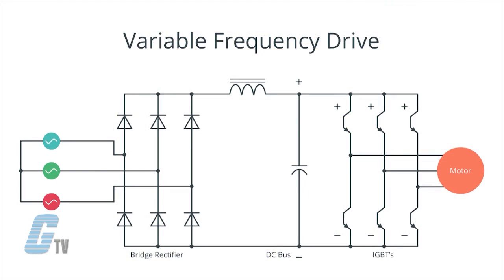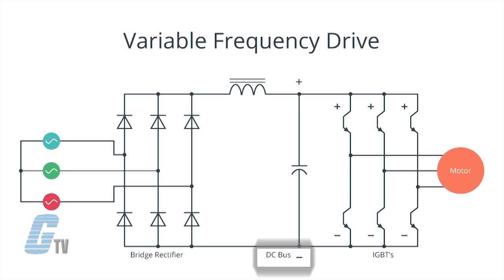When AC voltage comes into most drives, it enters a bridge rectifier. This is a group of six diodes that convert the AC to DC. In this form, the DC voltage is still not smooth and has some ripple. A DC bus system is in place with usually a capacitor to help smooth out the ripple.